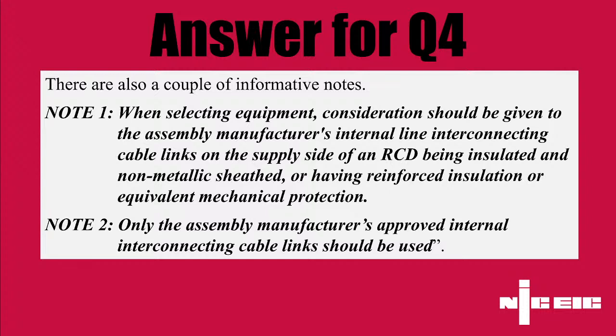So yeah, it's a good point, and it's one of those where I think it needs a bit of confirmation and clarification from the manufacturer, but I'm not aware of any big problems. Sometimes, although we've got a fear, it's easily comforted by the manufacturers saying, yeah, not an issue, we'll guarantee our internal wiring, our internal cables. But that's why that note specifically says you've got to use the manufacturer's ones. You can't go making your own, because they might not have the same rating and therefore the same degree of internal protection.